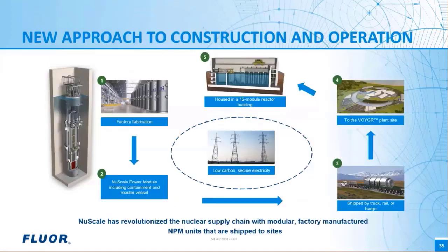The new approach to construction starts with the factory fabrication done in parallel with site preparation and plant construction. This gives you economy of production, controlled fabrication conditions, and a stable and skilled power module workforce who's producing these en masse, with improved cleanliness, quality, and repeatability. Then the power modules are shipped to the site either by barge, rail, or road, depending on the site, as shown in that third graphic. Road shipment would require that the power module be shipped in three sub-assemblies. So you would disassemble the lower containment vessel head, the reactor vessel, and the upper containment vessel, and they can be easily reassembled at the site.